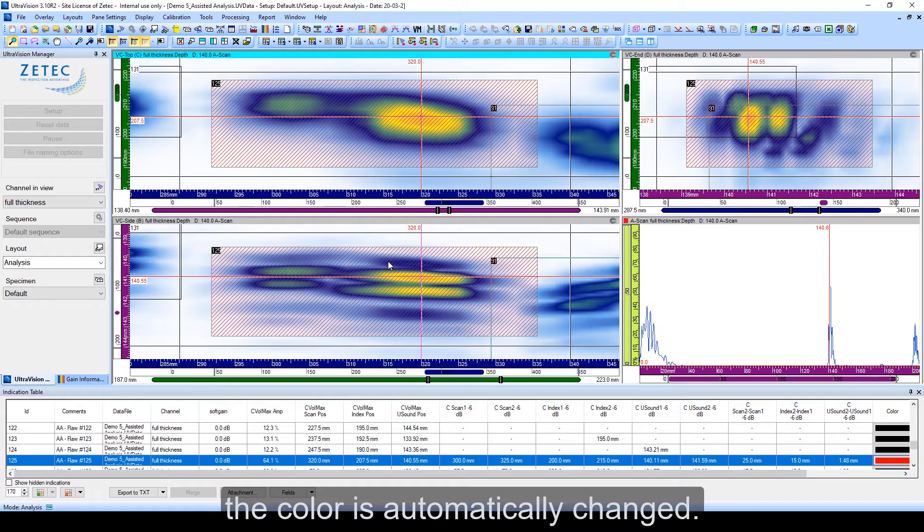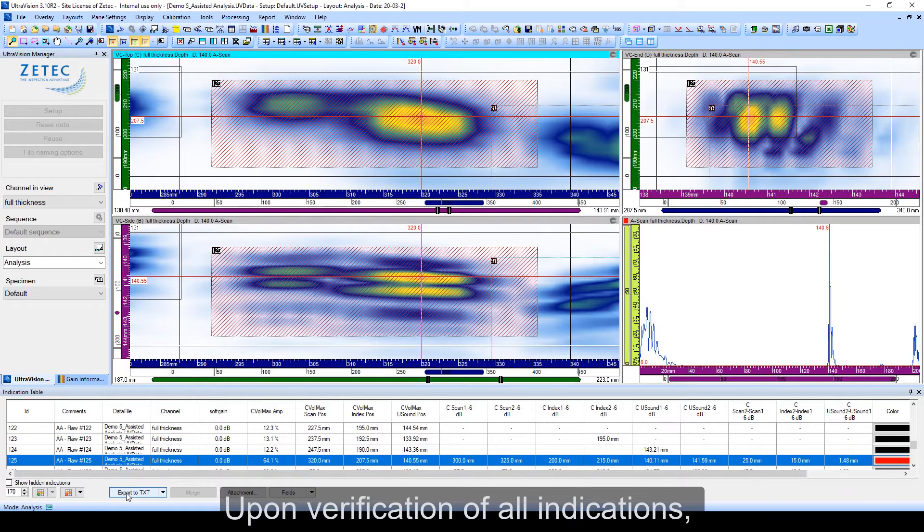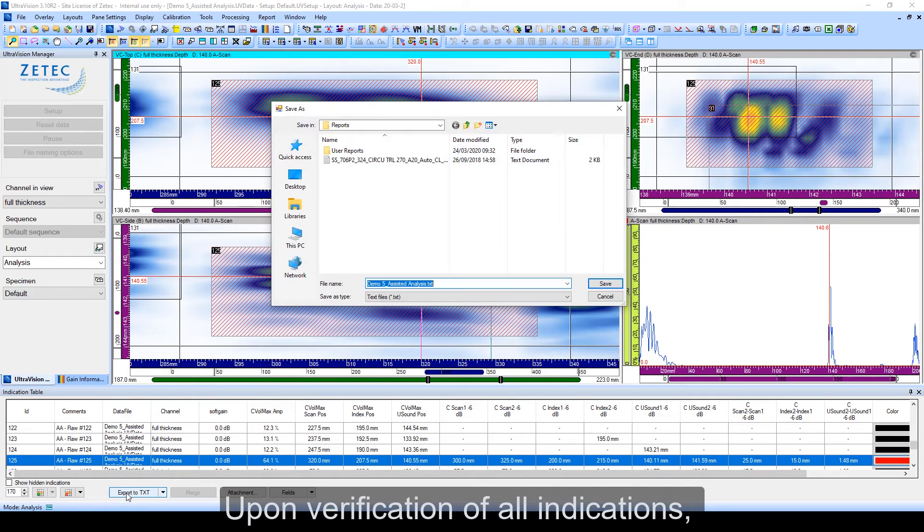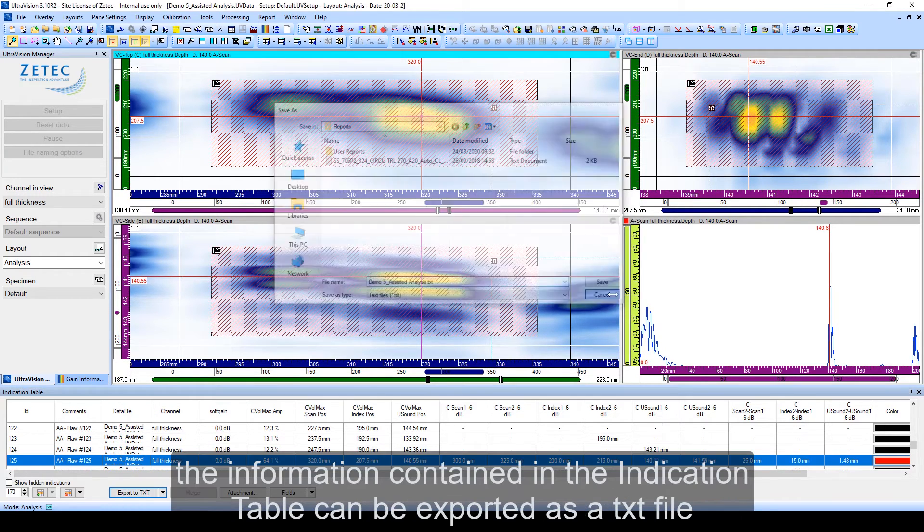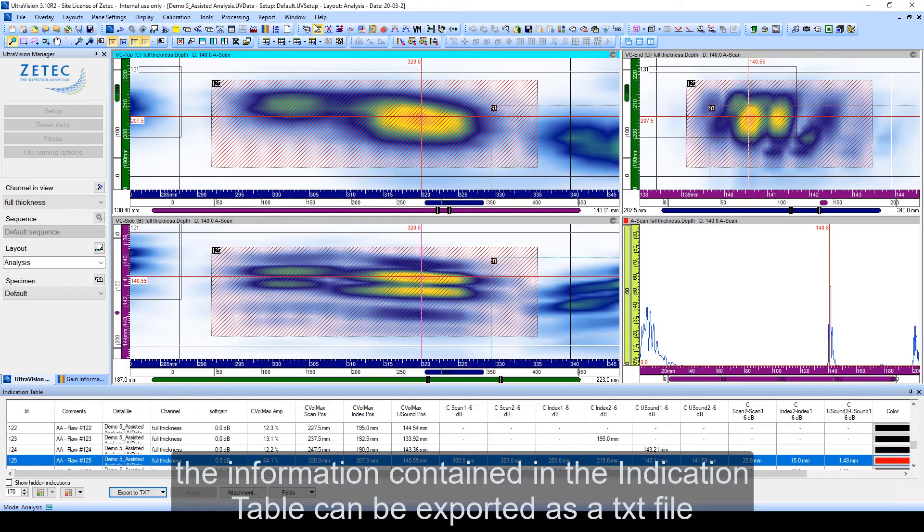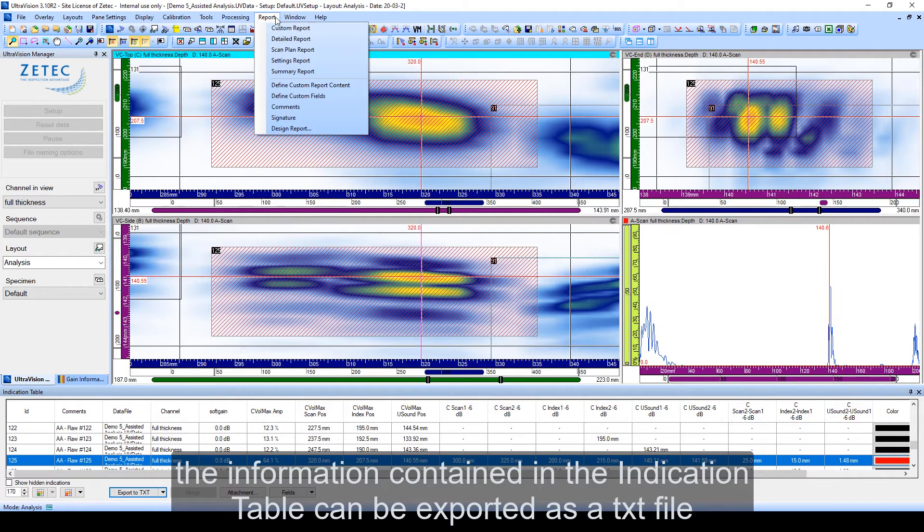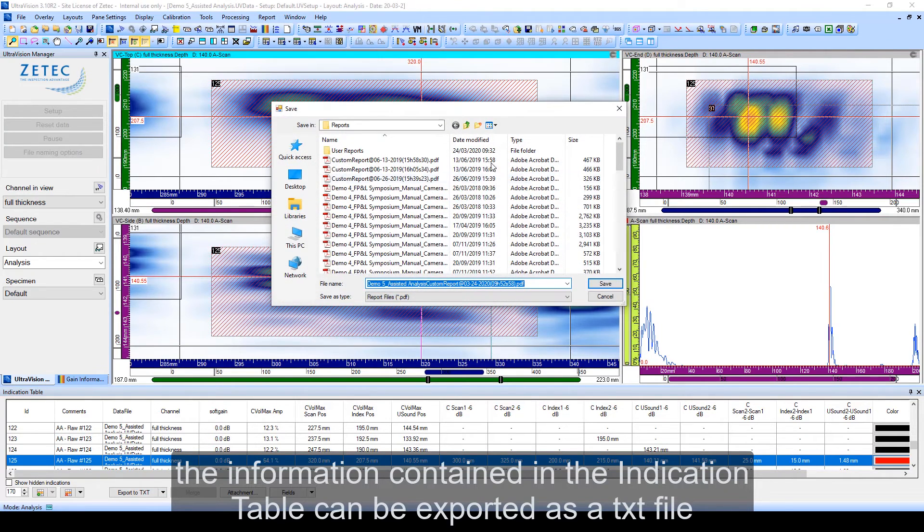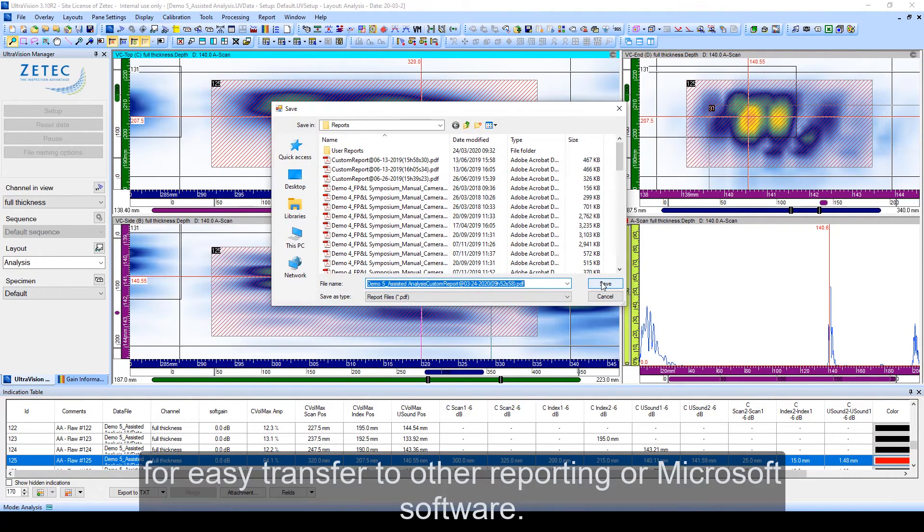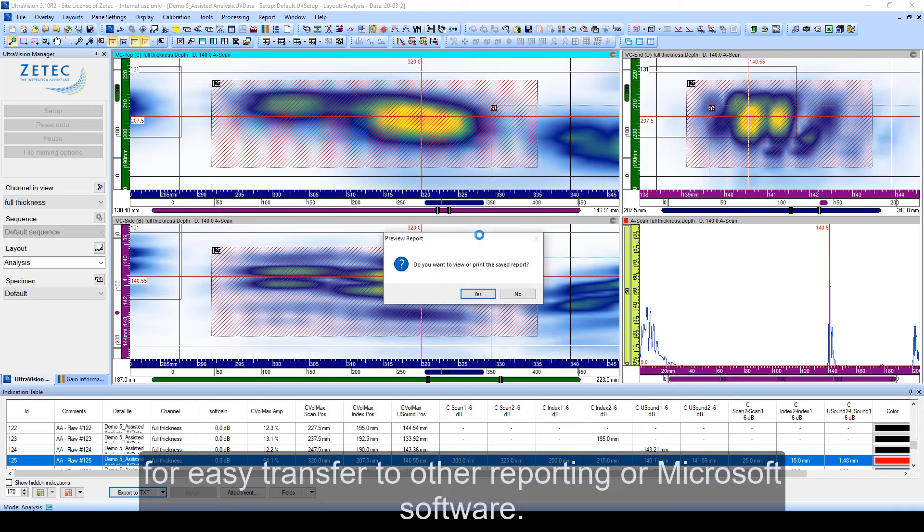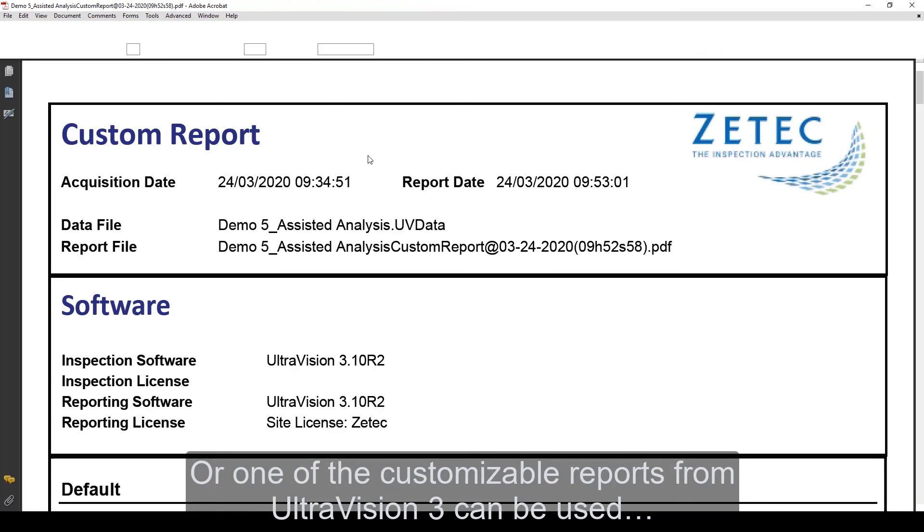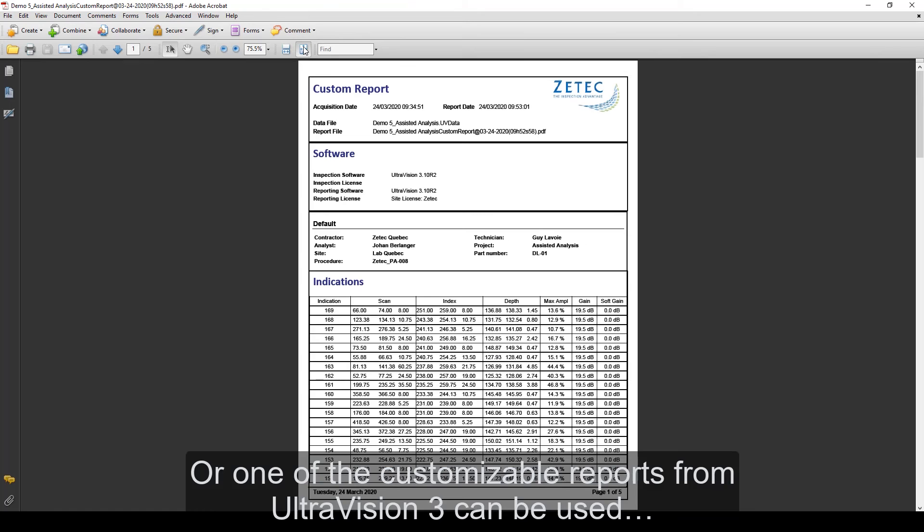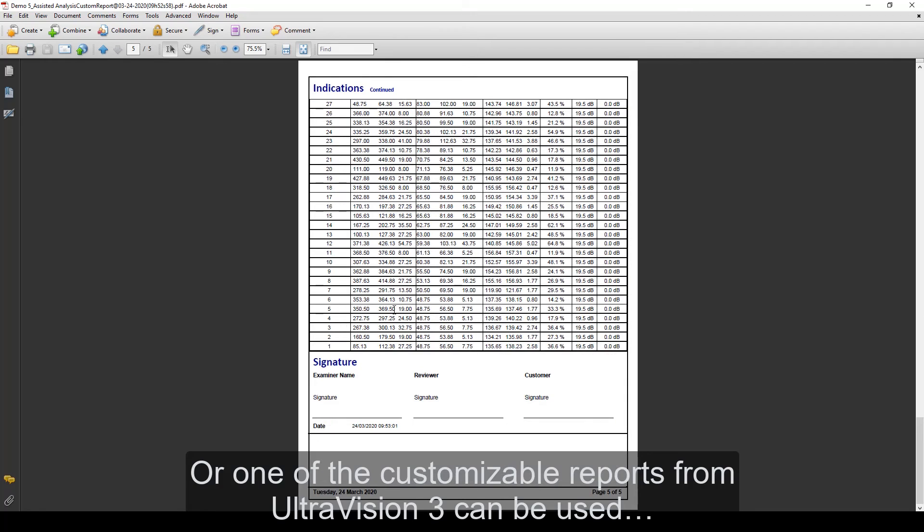Upon verification of all indications, the information contained in the indication table can be exported as a TXT file for easy transfer to other reporting or Microsoft software. Or one of the customizable reports from UltraVision 3 can be used.